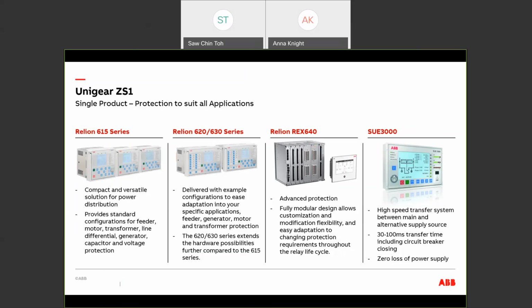Next, I would just like to touch on the SUE 3000. The SUE 3000 is the relay that we use to perform high-speed transfers between the main and alternative supply sources, ATS in short. Combined with the VM1-T cubicles, we can achieve a transfer time of 30 milliseconds. If we combine it with standard circuit breakers, the transfer time will be around 100 milliseconds. Together with these units, we make sure there is zero loss of power supply to your plant.